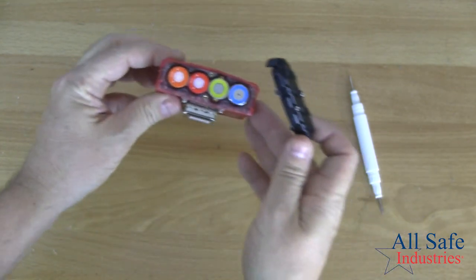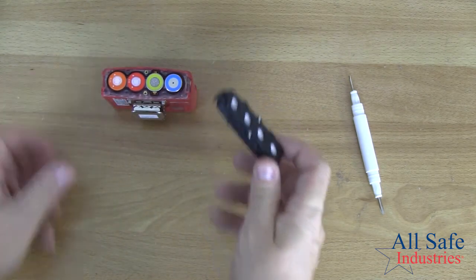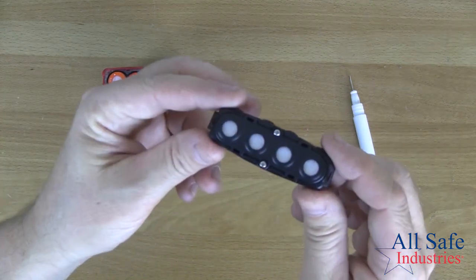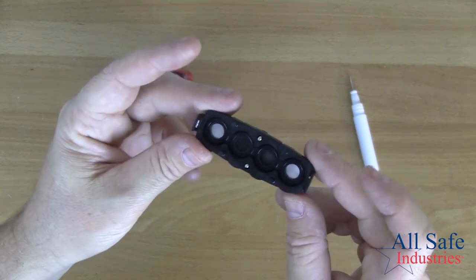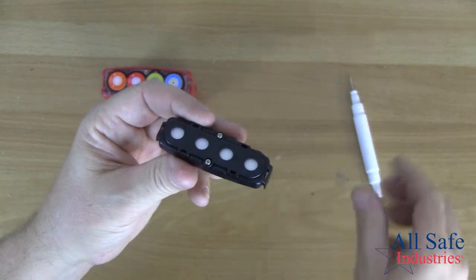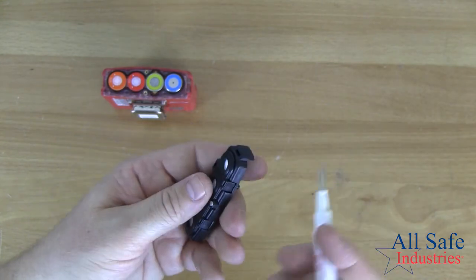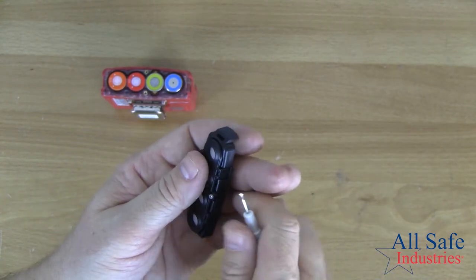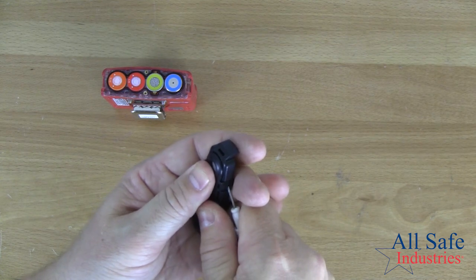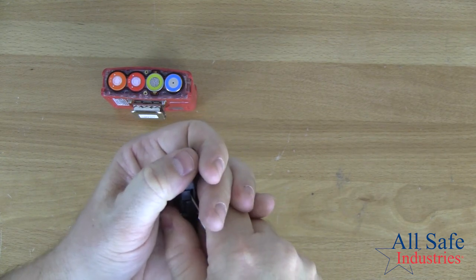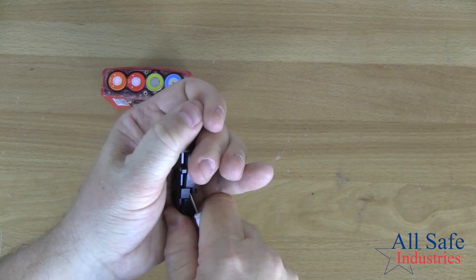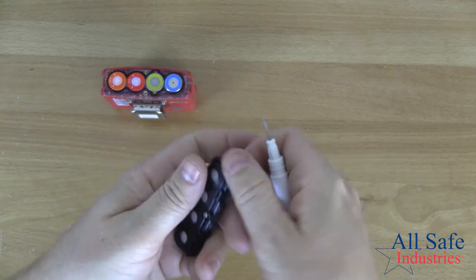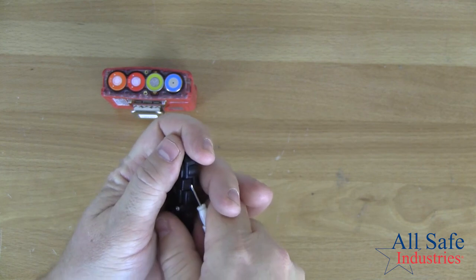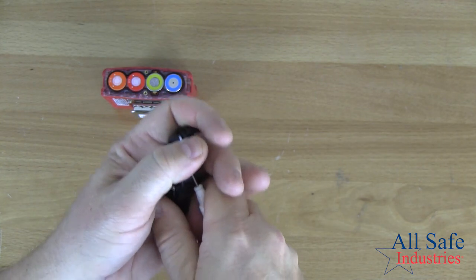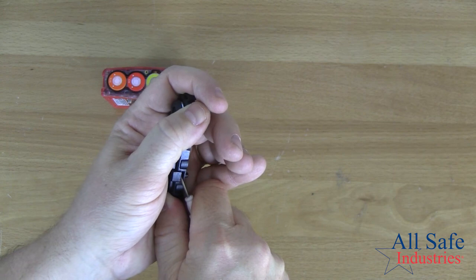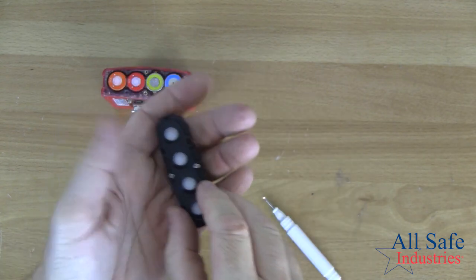Now I'm going to set the meter off to the side for a second because I want to show you a couple other maintenance items. This sensor retainer actually has a couple layers to it because there are some filters inside here that we can change. So I'm going to take my handy dandy screwdriver here again, and I'm going to release this top cover just by prying up on these little tabs. And I'm going to go ahead and just lift those up on all four tabs on both sides. Well, there's 2 tabs on each side, total of 4. And once I've got that released, you'll see the filters that are inside here.